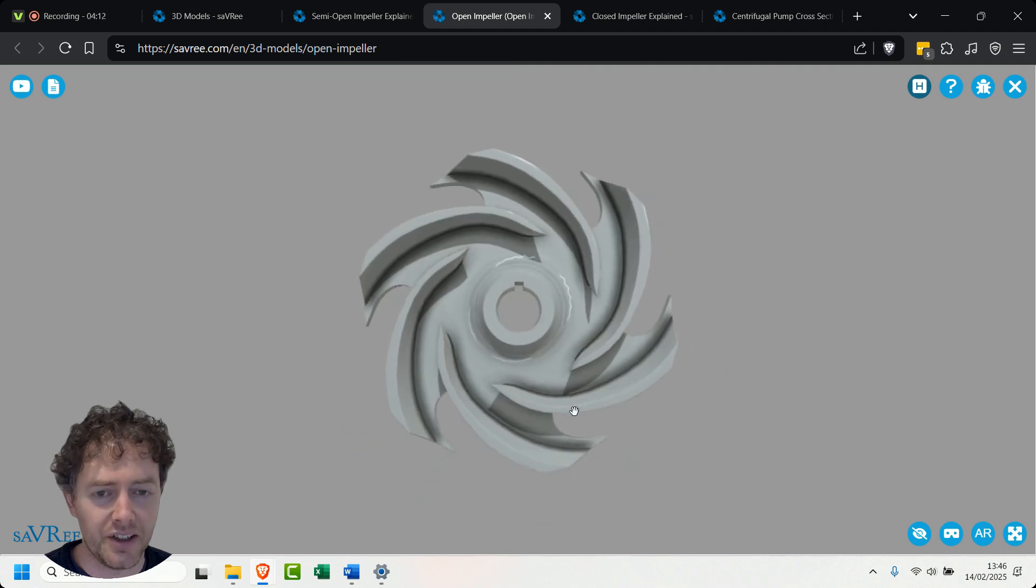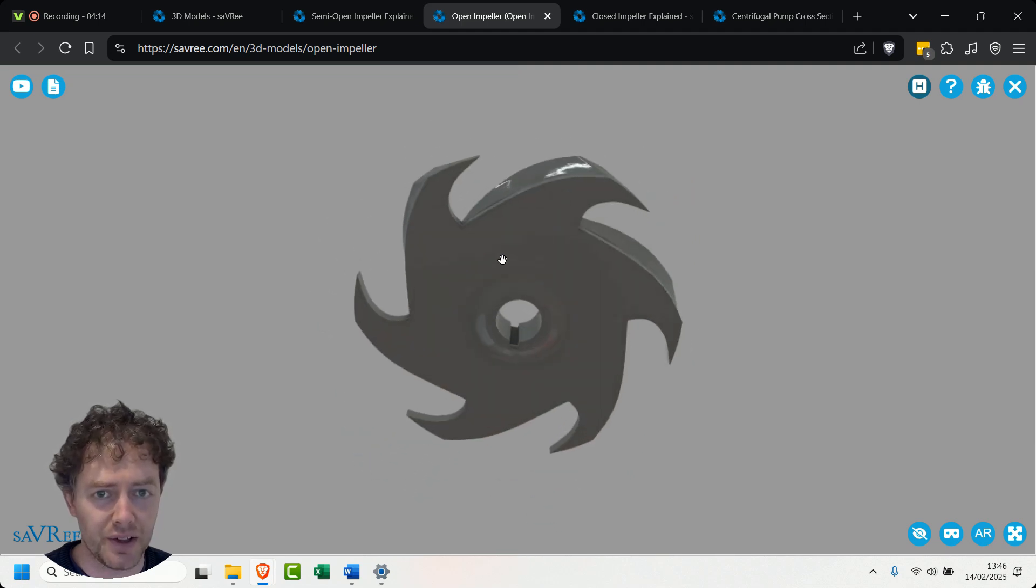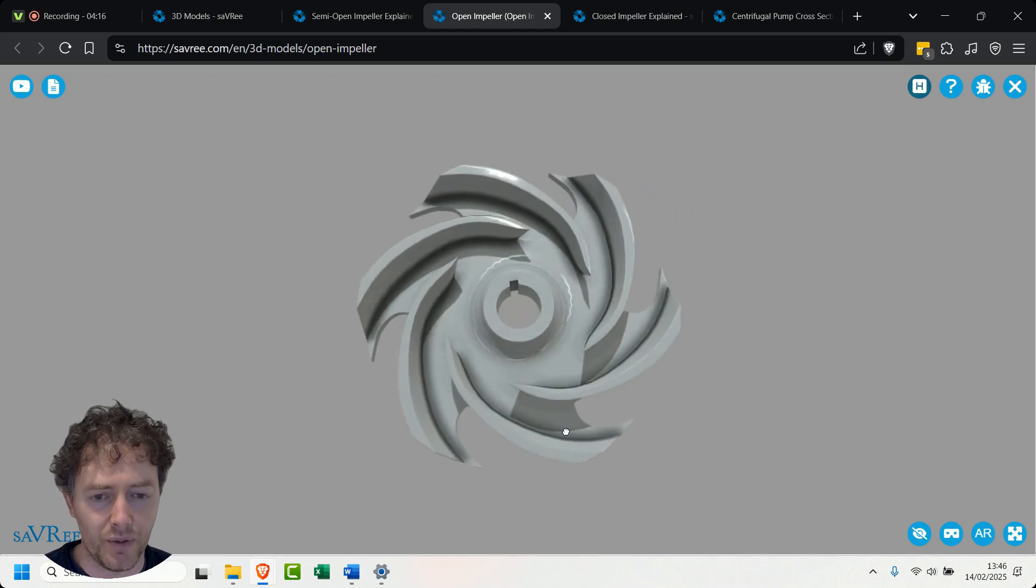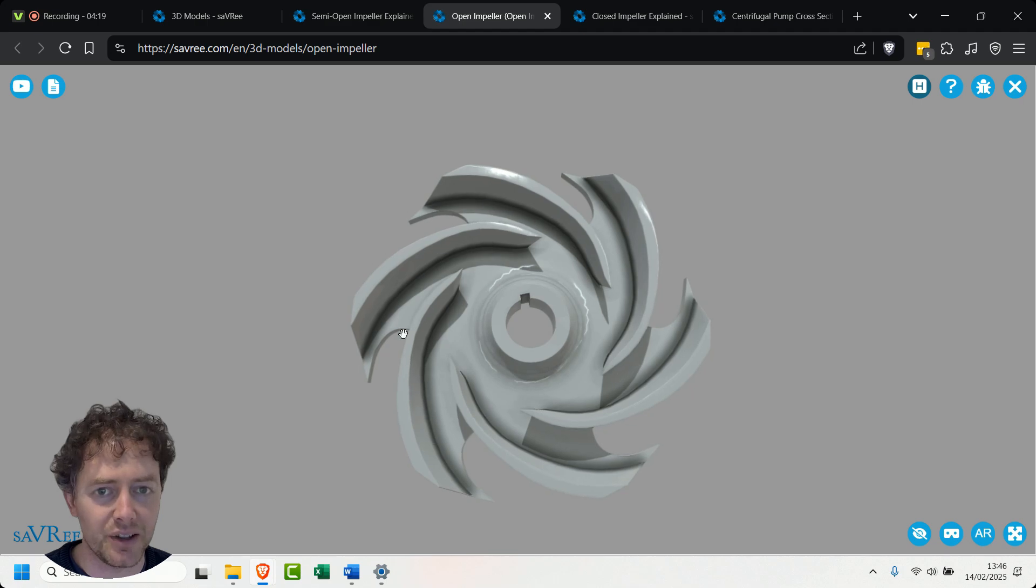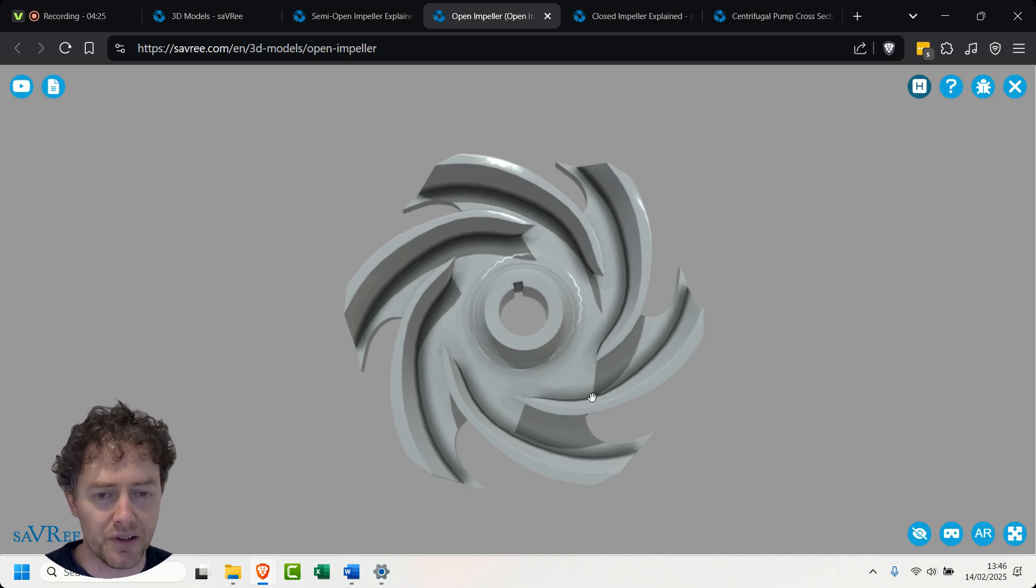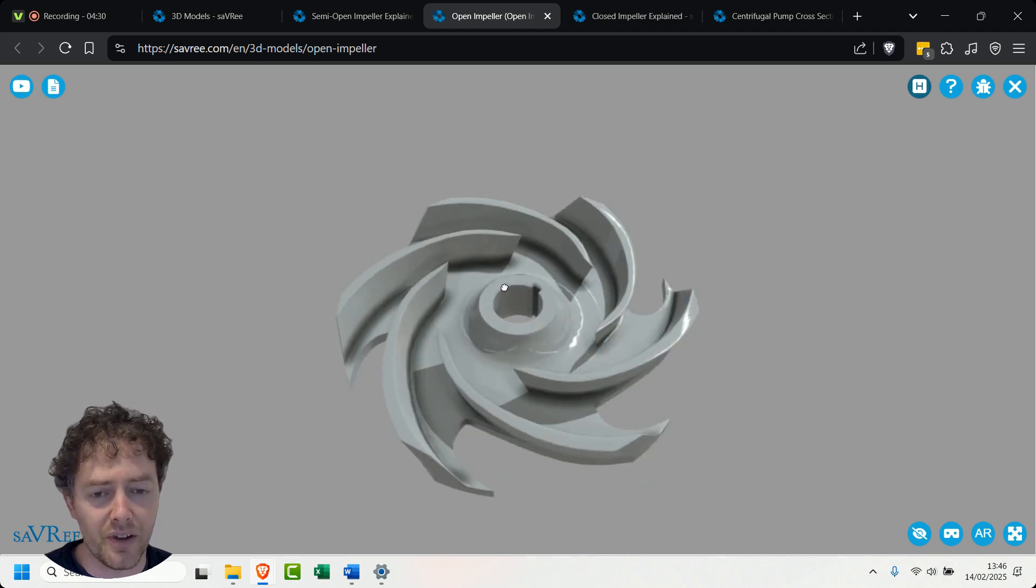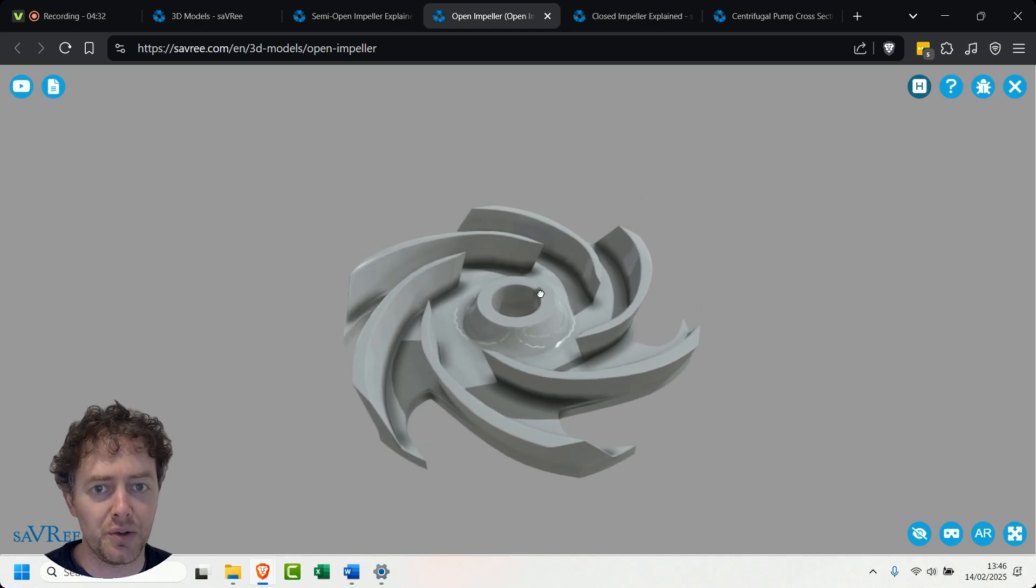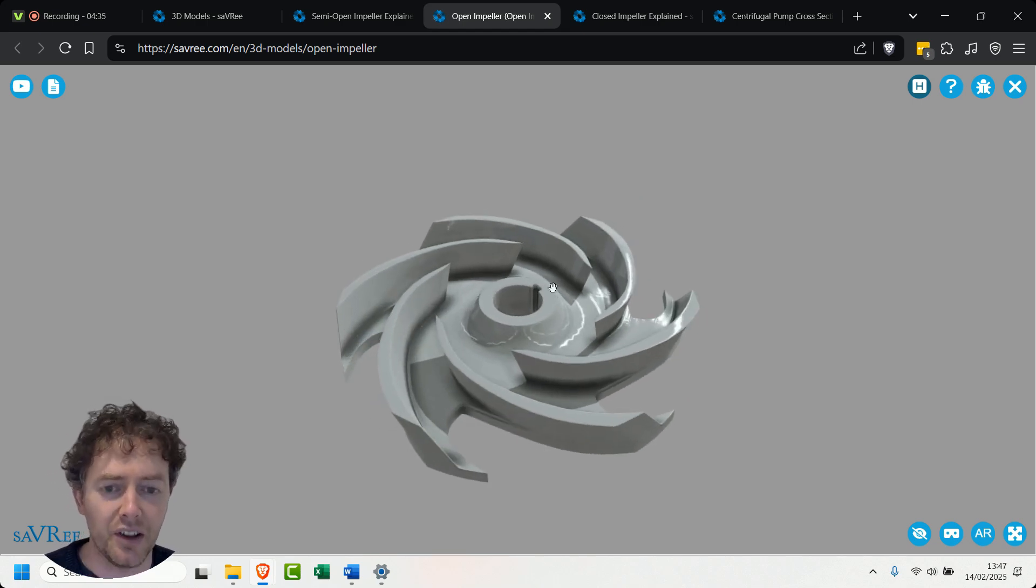Then you see again the shroud this time is very small and we've got the vanes and that's all it is. That is the entire impeller on its own. This one is well suited for when we have a large amount of suspended bodies so now we're pumping a slurry or some kind of sludge or something like that. I can tell you that this type of impeller is used with sewage pumping systems.